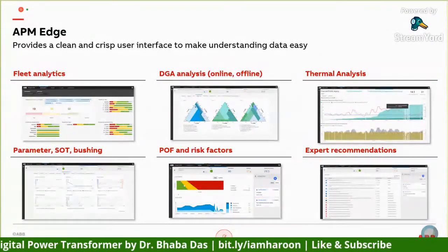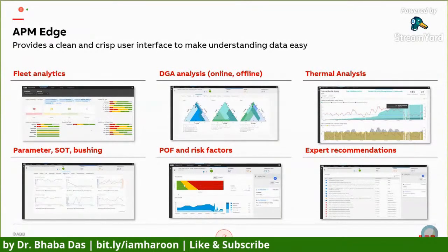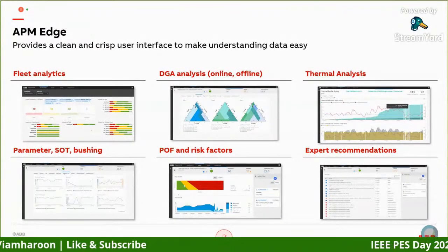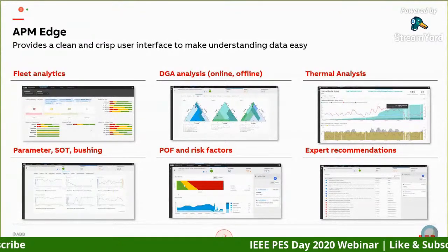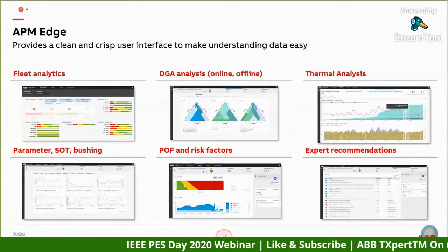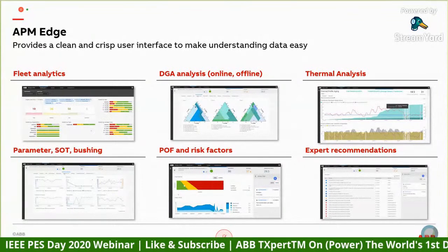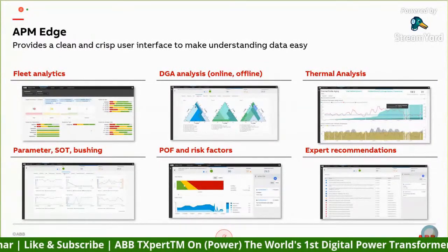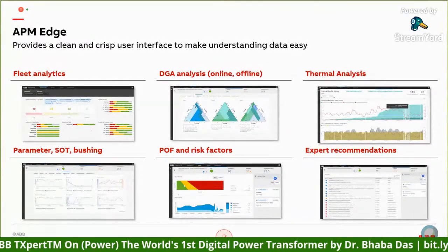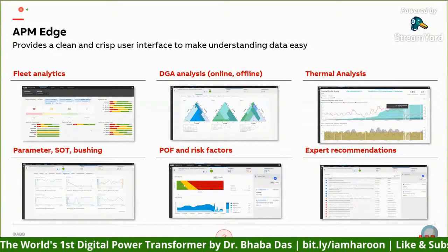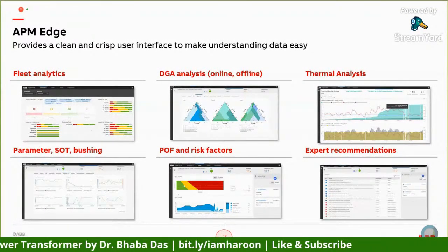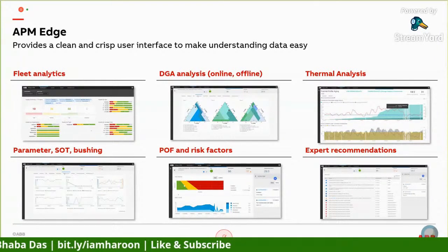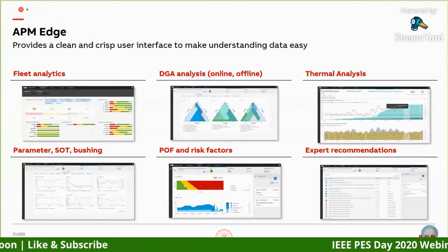Then we also do thermal analysis. We do a lot of different parameter analysis, power factors, bushing power factor, capacitance, standard oil test. Once we have all that data, we calculate the probability of failure and we determine what is the risk of the transformer. Then, based on that, the software gives you expert recommendations.